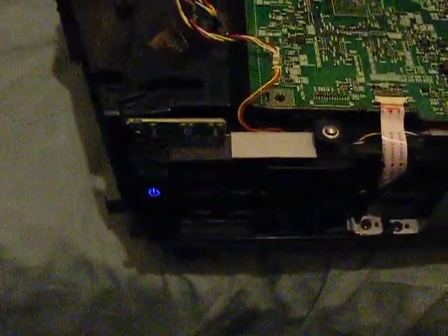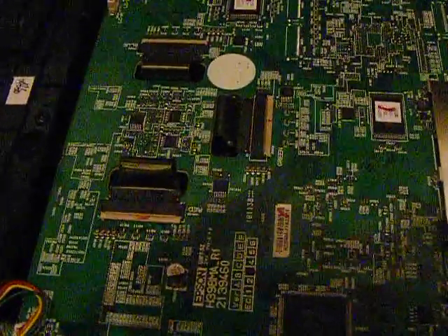Here we go. We've got power up, then flashing. You'll hear the orange flip. There you go, orange flip. Lamp and front shutter will open - lamp, front shutter open. And then all of a sudden, we will see error. I've replicated the same fault on this working machine as is what is on your machine.